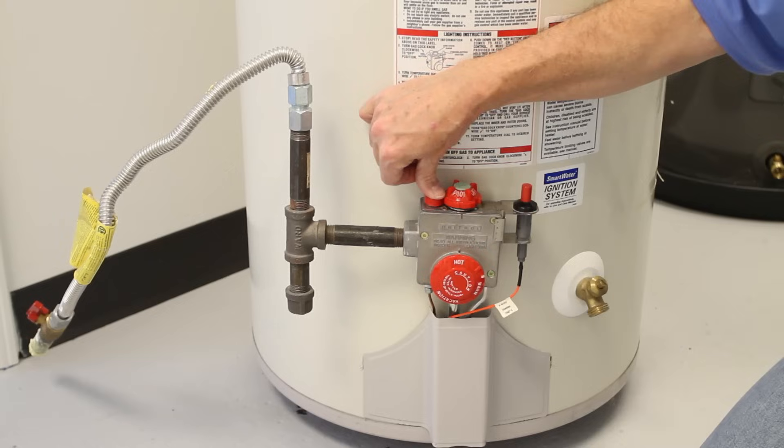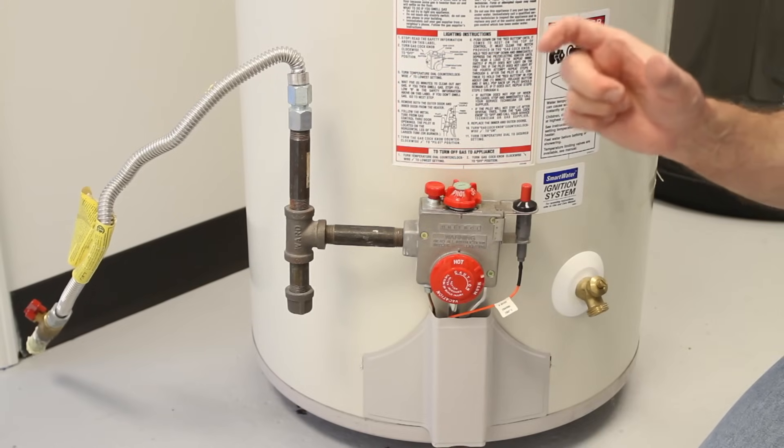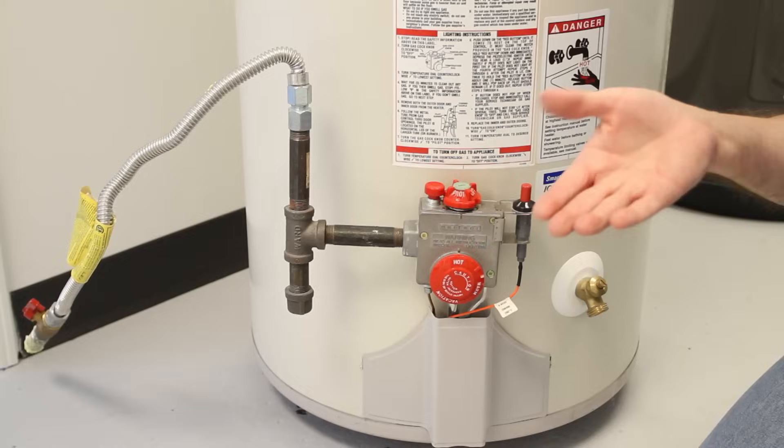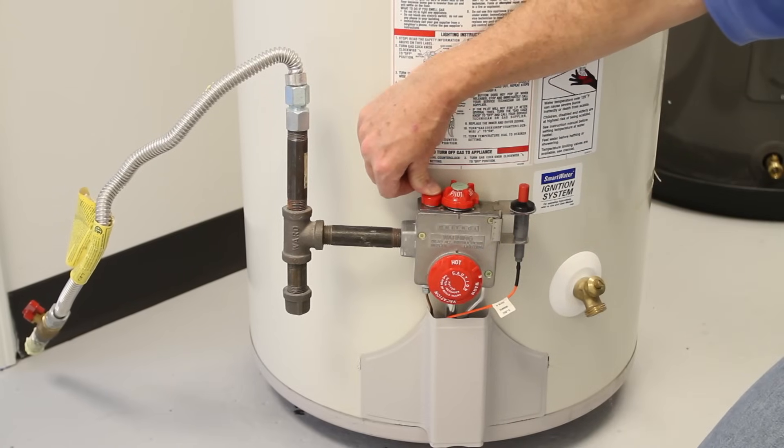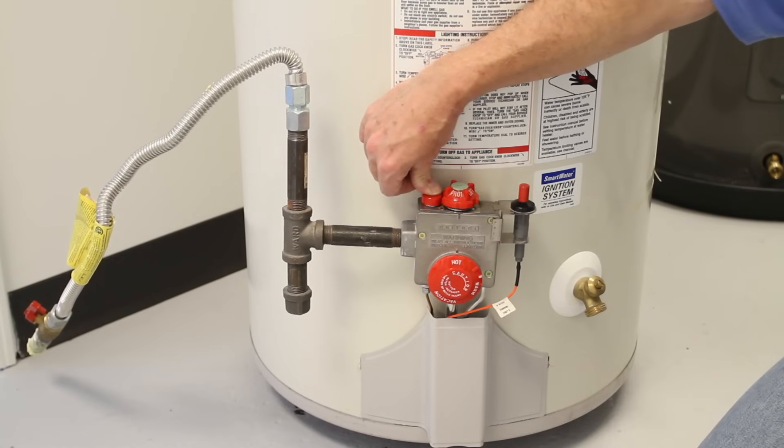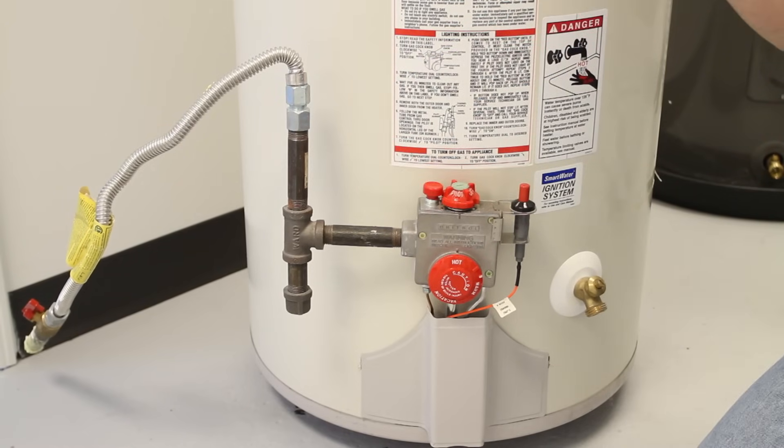And if you release this before the thermocouple is warm enough, the supply will cut off and the pilot will go out. So this override, you simply need to do it long enough so that the thermocouple will leave the supply on after you let that button up.